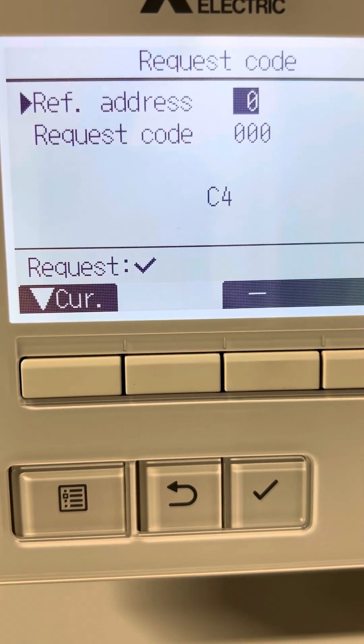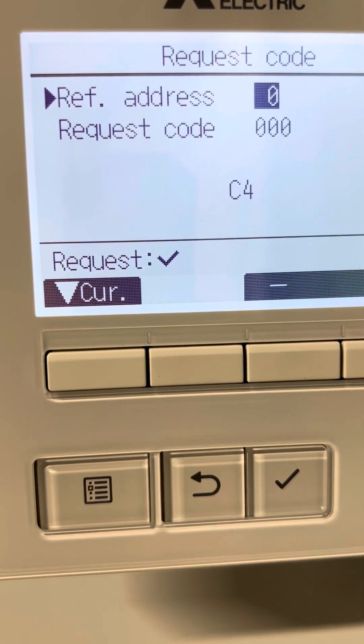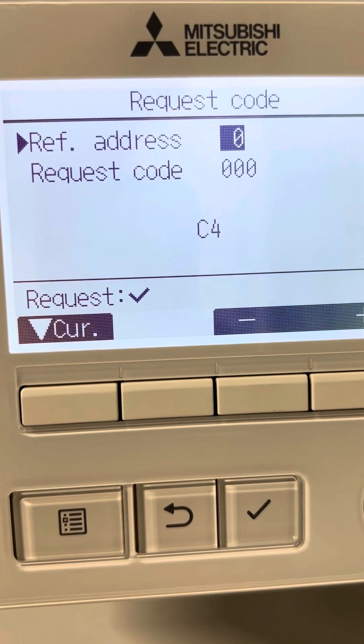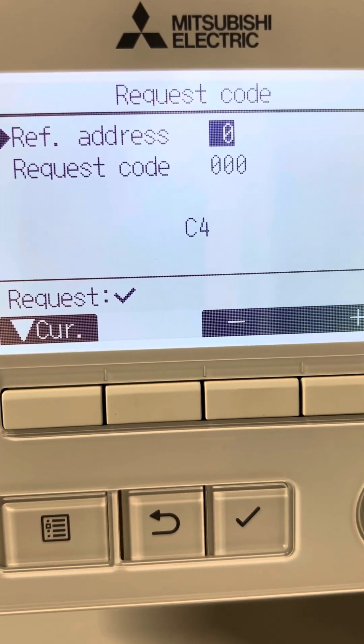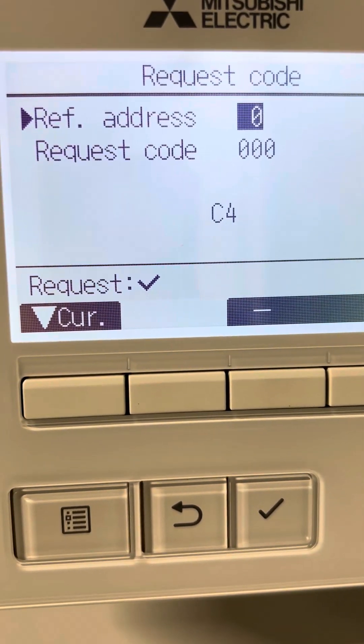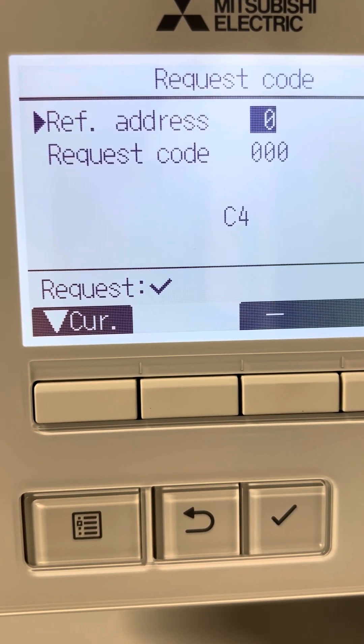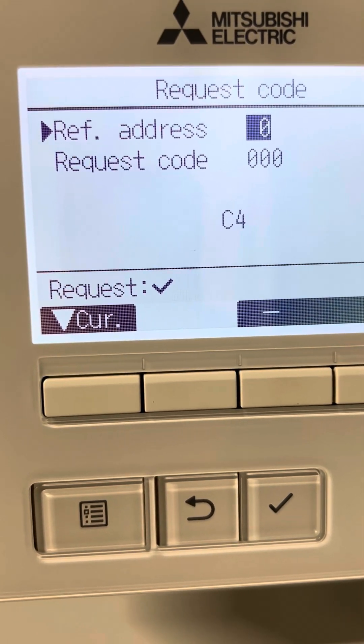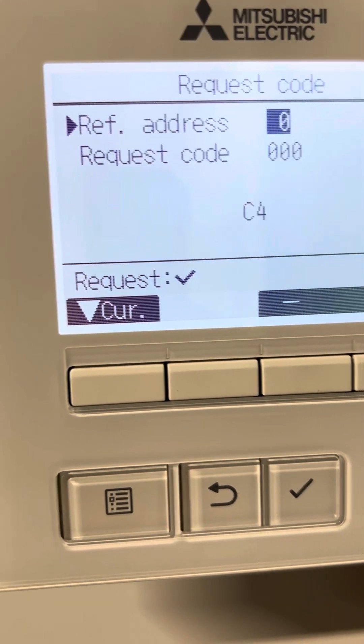When the unit is stopped or only the fan is running, and the number — in this case number 4 — means the compressor is on. The numbers can vary from zero to eight, and the character indicates different states, which includes four-way valve energized, solenoid valve on, or compressor on or off. I will put all those details in the description.